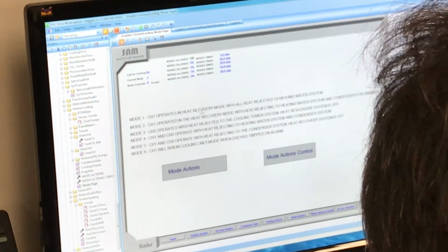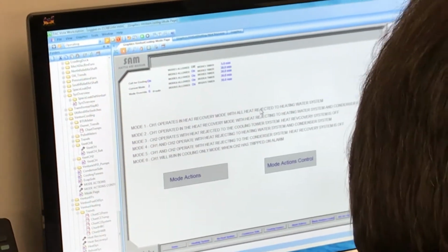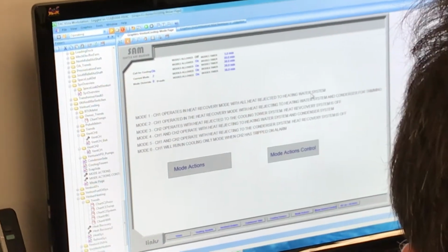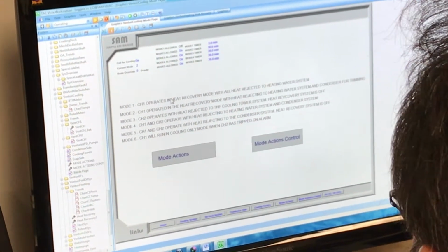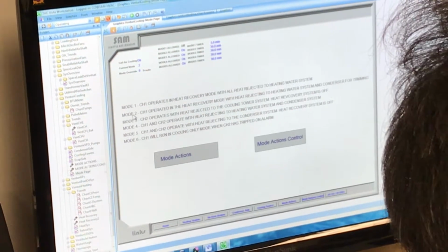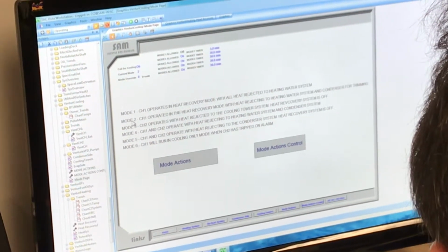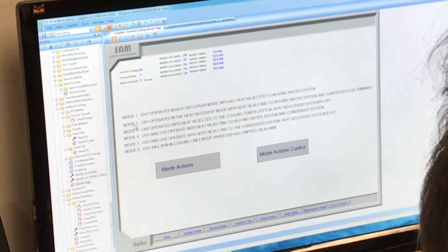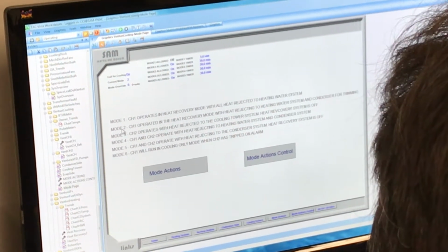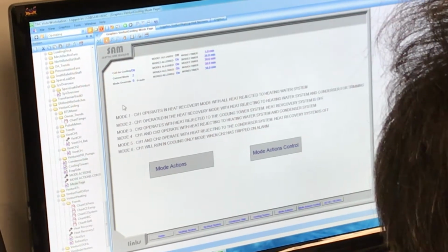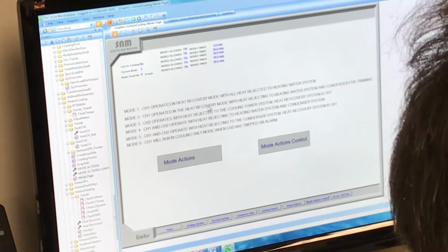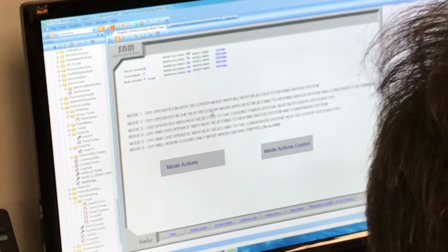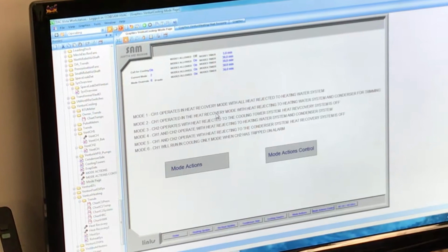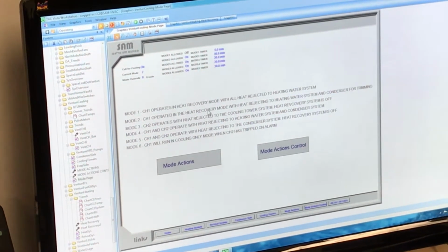So let's just go over the modes a little bit. Mode 1 we talked about, all the heat's rejected to the heating water system. We're not going to be using that much. Mode 2 is going to be your general mode of operation because it's kind of like regular chiller heat exchanger operation, to where it's in the heat recovery mode. It takes the heat in and sends it to the water system, and it also sends it out to the cooling towers for trimming so it doesn't get too hot.